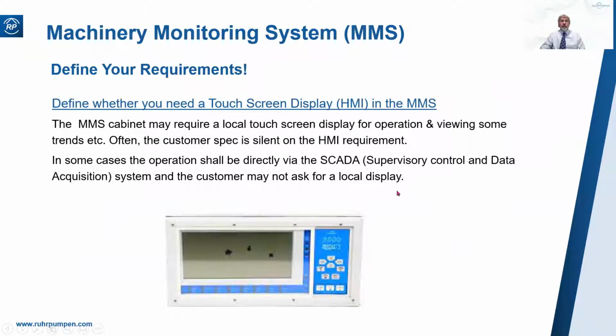Likewise, do you need a touch screen display on your panel? Also called an HMI, which is human machine interface, which is not something scary out of Skynet. It's something you have on a Bentley Nevada system. It might well be that you're feeding directly to the SCADA system, and so you don't need a local display. Local displays are quite expensive.